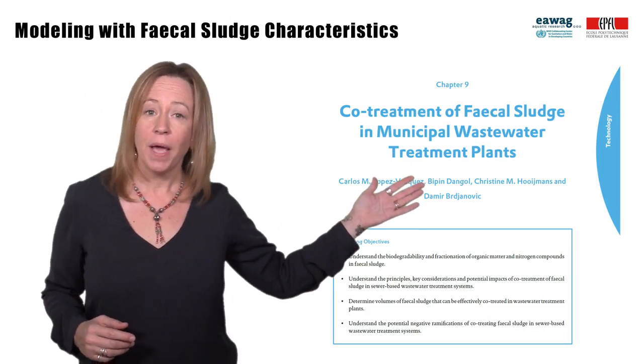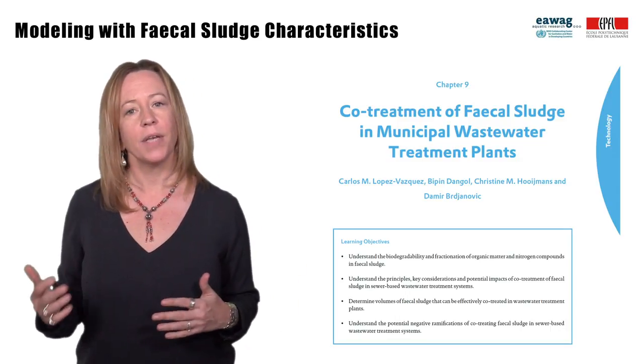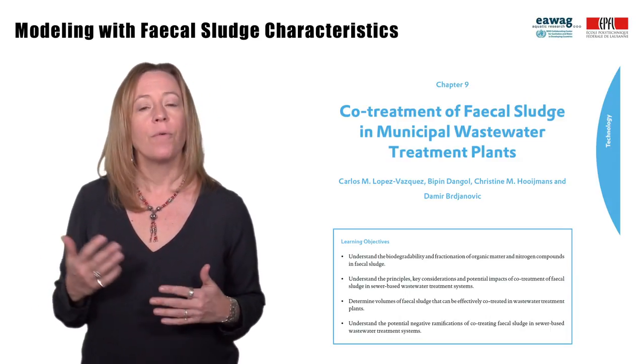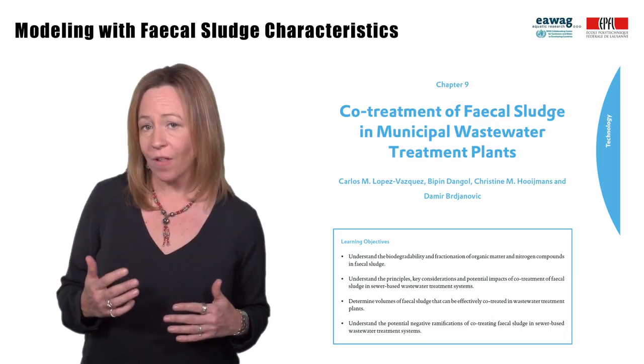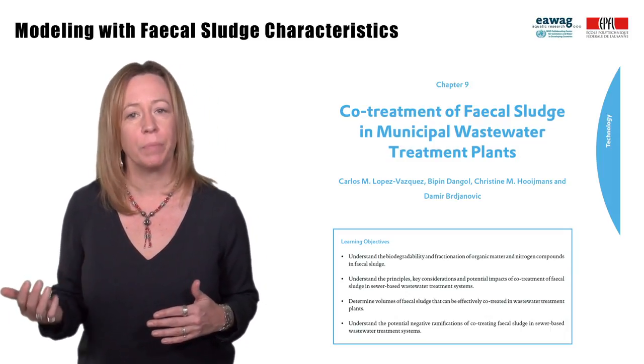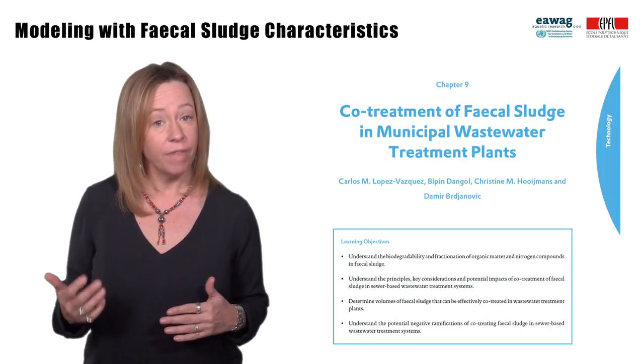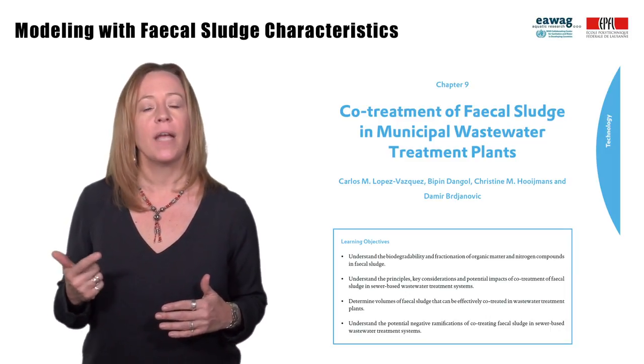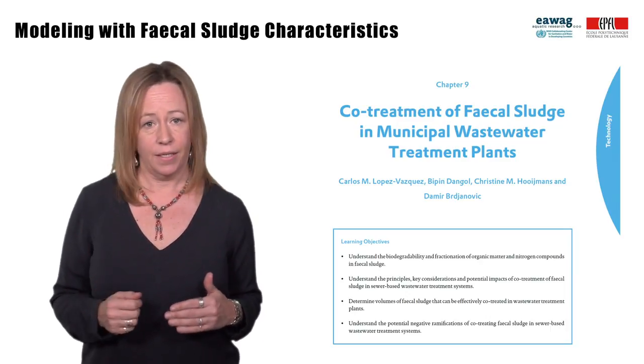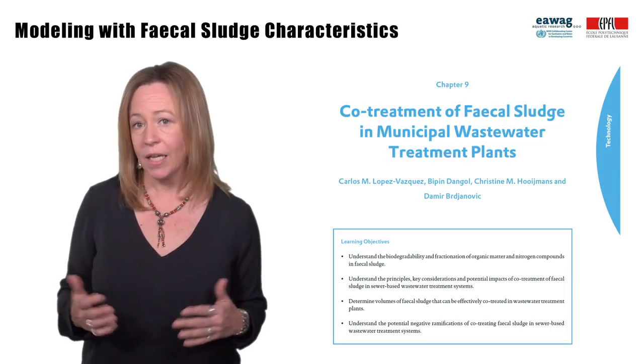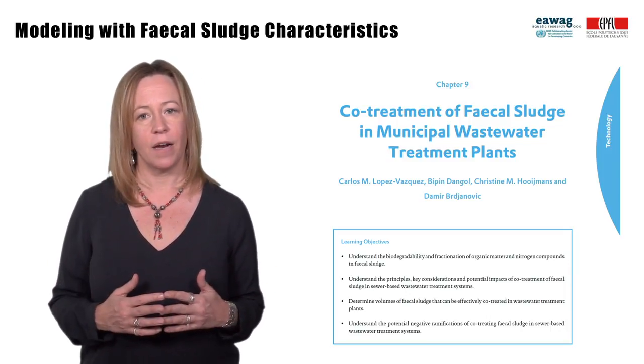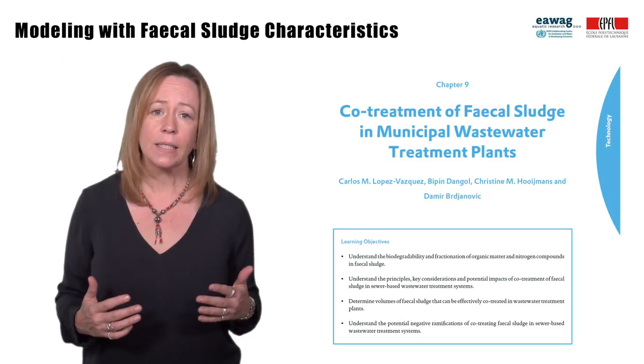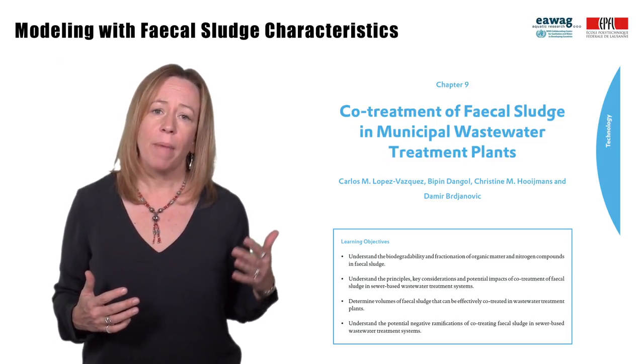Chapter 9 in the fecal sludge management book covers detailed modeling in more depth. It covers the impacts that fecal sludge with different strengths, concentrations, degradable organic matter, and inert solids have on the loading of wastewater treatment plants. Impacts on operations that can lead to failures include reduced effluent quality, maxed out aeration resulting in aerobic processes turning anaerobic, incomplete oxidation, filamentous bacteria, and overloading settling tanks and clarifiers. Overloading of anaerobic systems can also lead to inhibition of biological processes and increased sludge production, maxing out solids handling.